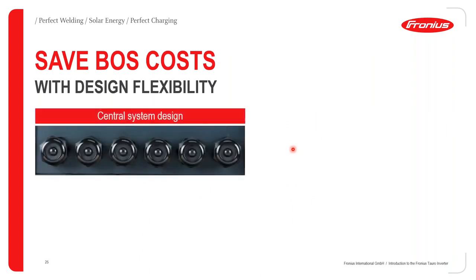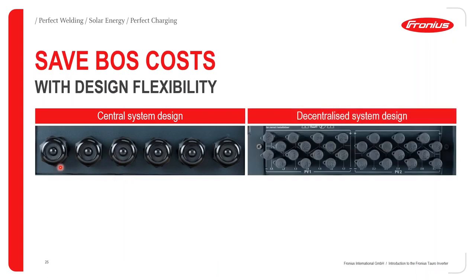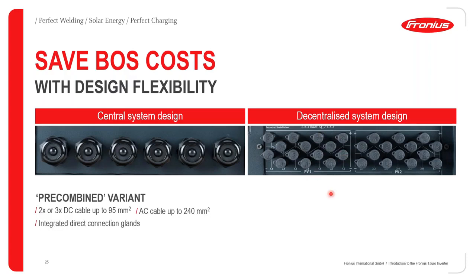So how to therefore save the BOS costs with design flexibility as far as the central and the decentralized designs are concerned? When we talk about the centralized design, which is now the pre-combined version of the inverter, we are talking about the possibility to come in with up to 6 DC connections. So this can be 2 minus connections, 2 plus connections, and up to 6 connections in total. Looking at the decentralized version, we are talking about the possibility to connect your inverter directly from the PV array strings. So you can have a maximum of up to 22 MC4 plugs included in your decentralized or the direct inverter version.